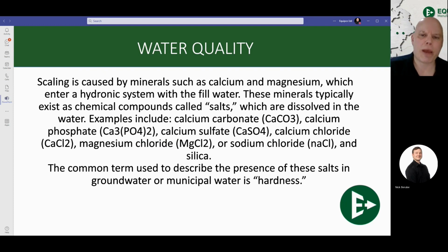So basically what you have, all these sulfates and calciums and all this stuff, these are referred to as basically your water hardness. There's also iron in water, which is your ferrous material, which can lead to that pitting, as I showed at the beginning of this piece here. But these guys here are going to lead to your scale buildup. There's a bit of a difference between iron buildup and scale buildup, but essentially they're all going to be inside of that system, not allowing for the best water transfer.